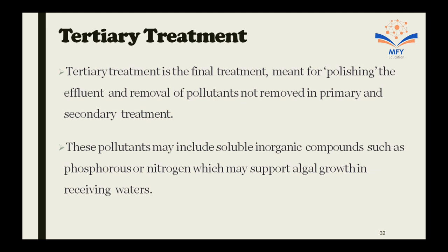Tertiary treatment is the final treatment means for polishing the effluent and removal of pollutants not removed in primary and secondary treatment. These pollutants may include soluble inorganic compounds such as phosphorus or nitrogen, which may support algal growth in receiving waters. It also removes organic materials contributing BOD or COD or color, taste, odor, bacteria, viruses, colloidal solids contributing to turbidity, or soluble minerals which may interfere with subsequent reuse of the wastewater.